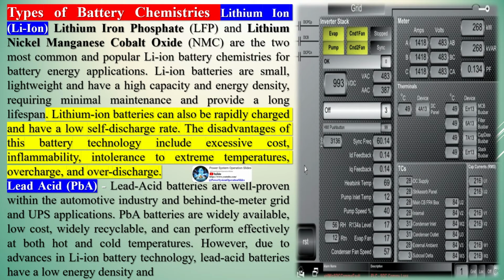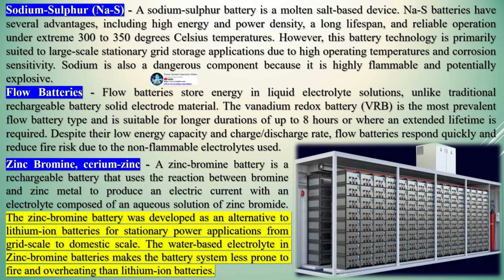Types of battery chemistries. Lithium-ion, Li-ion: lithium iron phosphate, LFP, and lithium nickel manganese cobalt oxide, NMC, are the two most common and popular Li-ion battery chemistries for battery energy applications. Li-ion batteries are small, lightweight, and have a high capacity and energy density, requiring minimal maintenance and providing a long lifespan. Lithium-ion batteries can also be rapidly charged and have a low self-discharge rate. The disadvantages of this battery technology include excessive cost, flammability, intolerance to extreme temperatures, overcharge, and overdischarge.